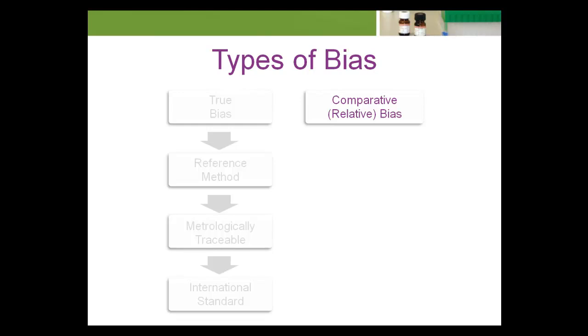Comparative or relative bias is the difference between an observed value and the calculated value of a consensus group for the same analyte. There are three types of consensus groups familiar to laboratories participating in control-vendor interlaboratory comparison or proficiency testing programs.